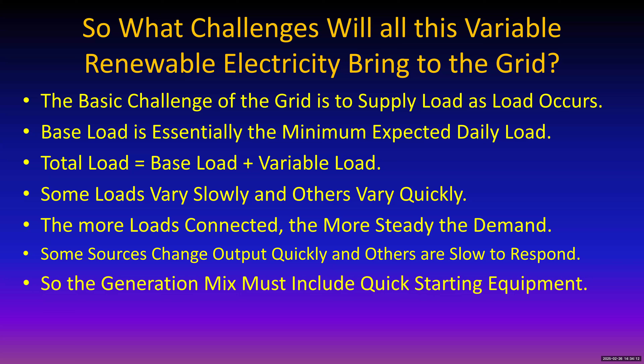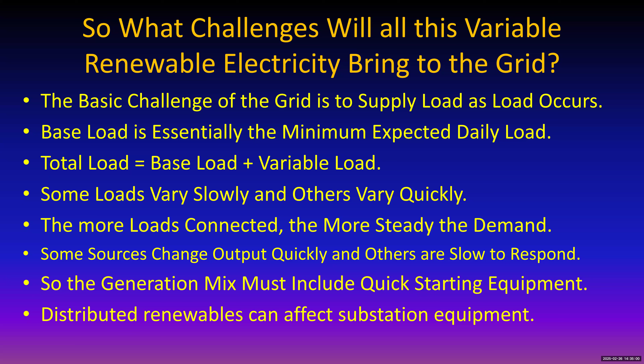It's also been demonstrated that distributed renewables can affect substation equipment. If you've got a lot of solar out there and start putting more electricity back into the distribution system than people need, it starts going back toward the substation, and this becomes, as opposed to a distribution system, a transmission system at distribution voltages. That's going to affect the equipment at the substation, so it needs to be thought about when managing these variable sources.